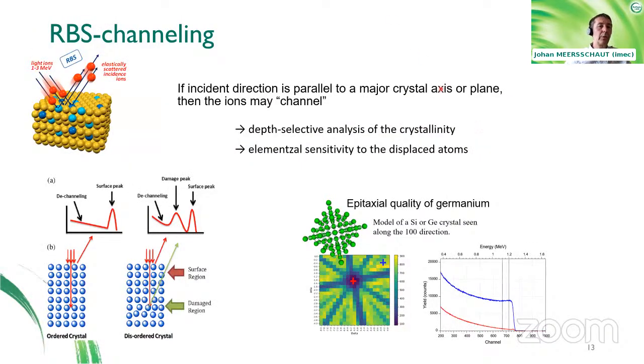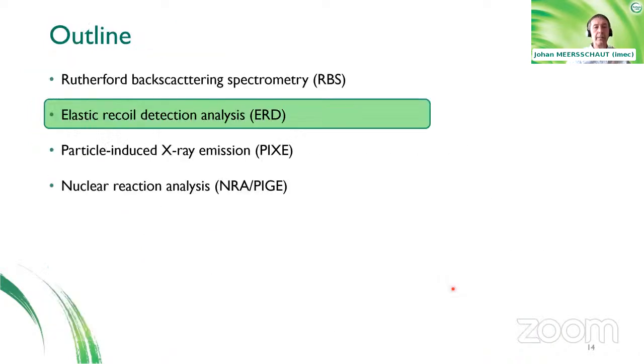A last technique which I would like to mention with respect to Rutherford backscattering is channeling. This is a technique where we are aligning the sample with the crystalline axis along the incoming or exiting axis of impingement of the ions, and it allows us to determine the crystalline axis of the sample under investigation. Now, if you would have a little bit of oxygen on the surface of such a sample, it would be superimposed onto the very intense signal which is coming from the substrate. And this is, you could say, a limitation of Rutherford backscattering spectrometry.